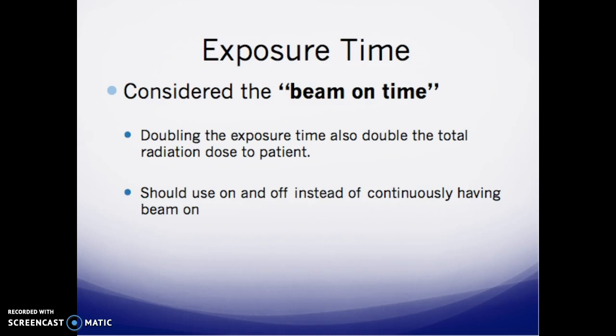Exposure time is the beam-on time. Doubling the exposure time doubles the total radiation dose to the patient. Fluoro should use an on-and-off pulsed approach — for example, if a doctor is waiting for the stomach to empty, they should tap the pedal on and off rather than continuously holding the beam on. Using pulsed fluoro reduces the direct beam-on time, which directly reduces radiation dose to the patient and operator.